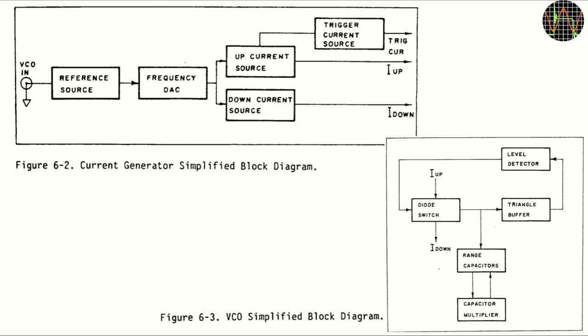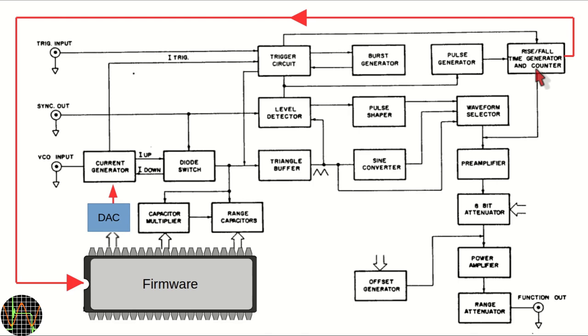You may wonder, how does the CPU know which digital word to use to produce a voltage that generates the desired frequency? The manual doesn't explain this at all, but I think the frequency error problem provides a clue. I think the CPU simply uses the built-in frequency counter to check if the commanded current with the selected range capacitor produces a frequency that is within the tolerance spec. This concept also means that frequencies are not as exact or stable as you might expect from modern generators where all frequencies are generated digital from a master clock. There is no master clock in the 8201 which is using a free running VCO and for the same reason you can only select frequencies through the four most significant digits.